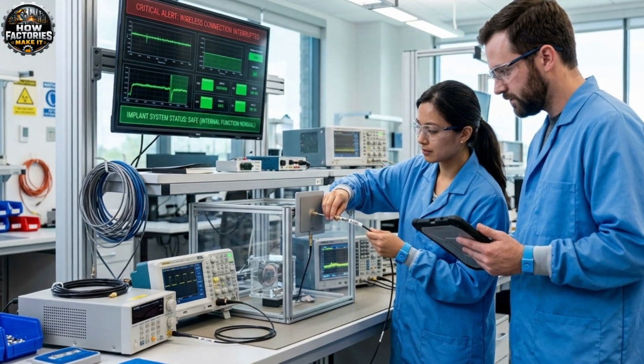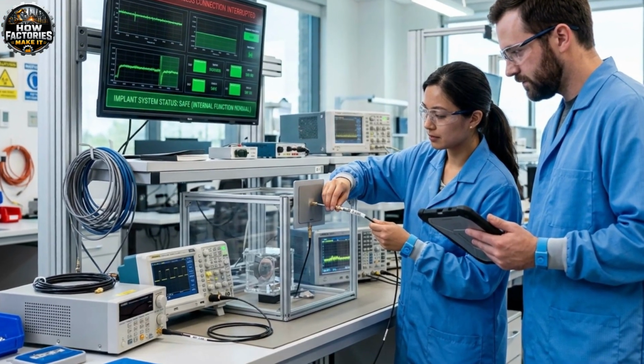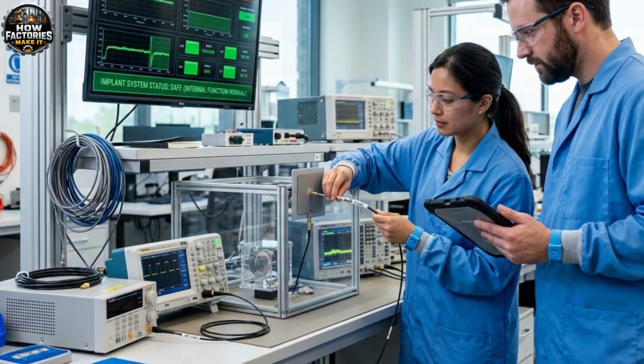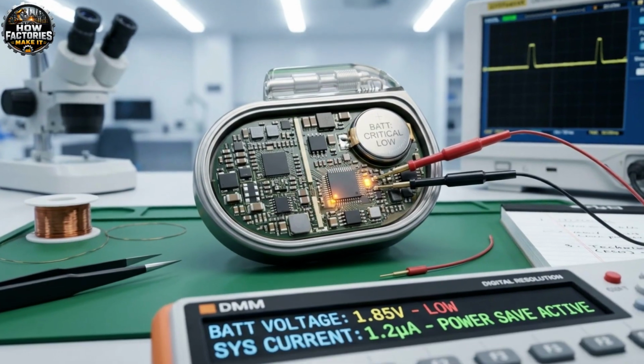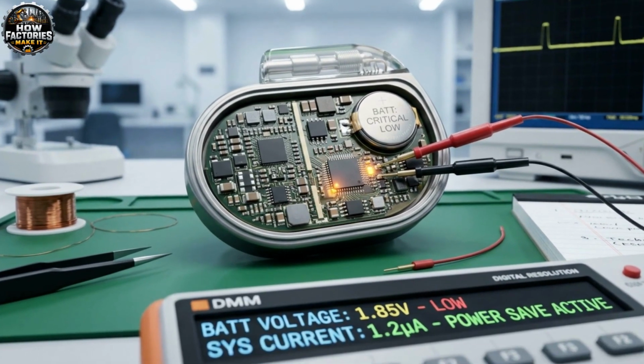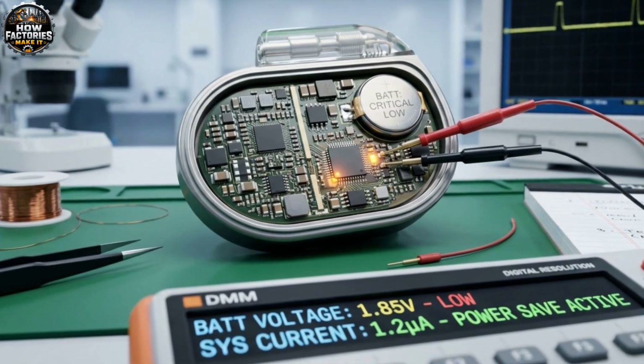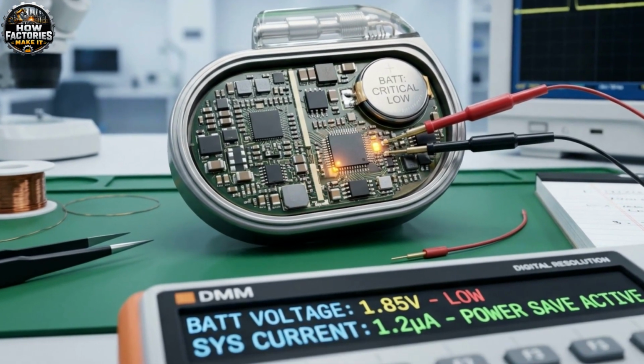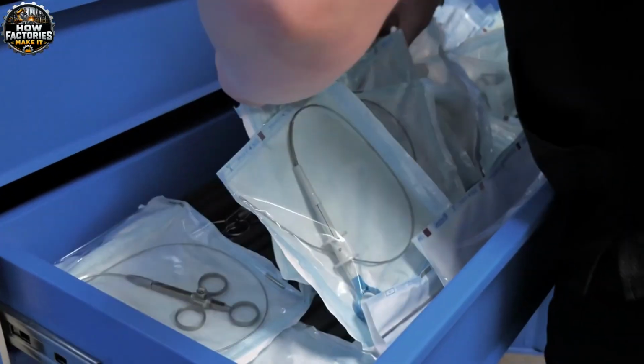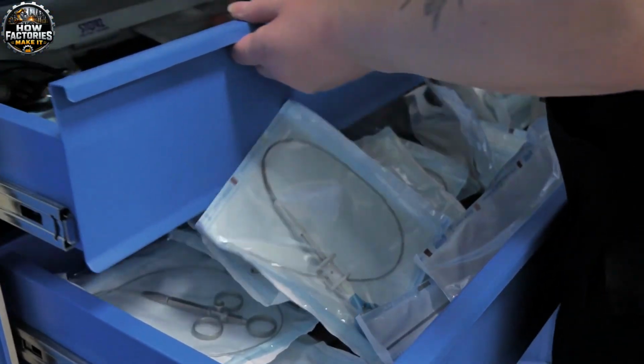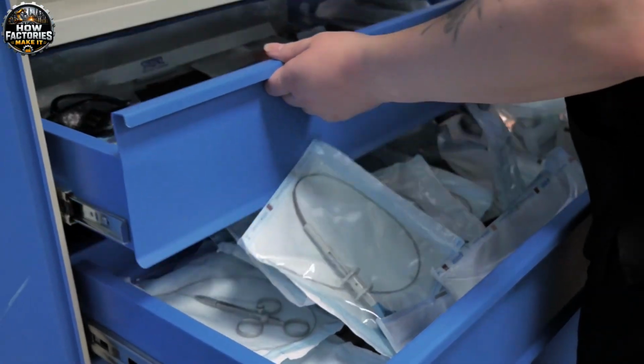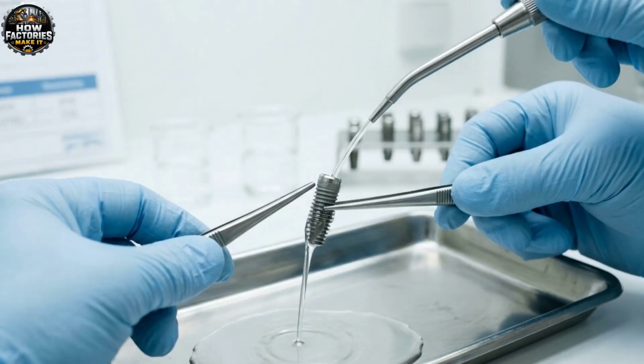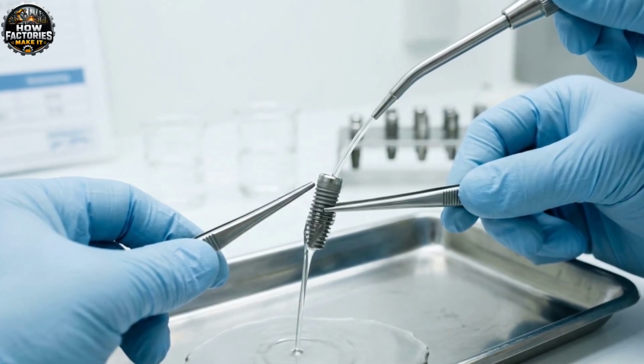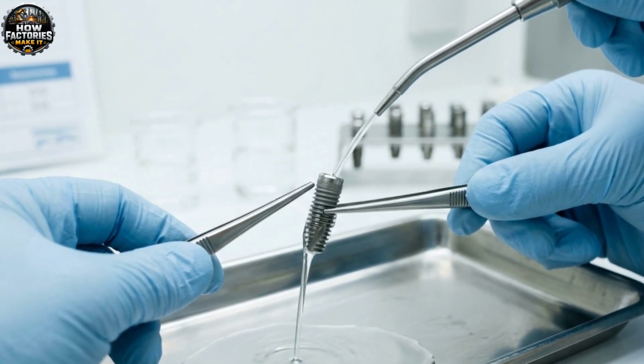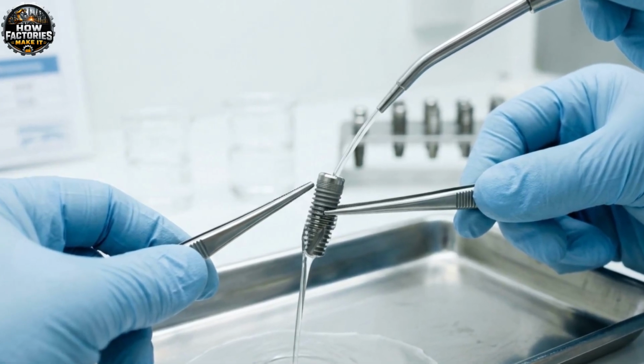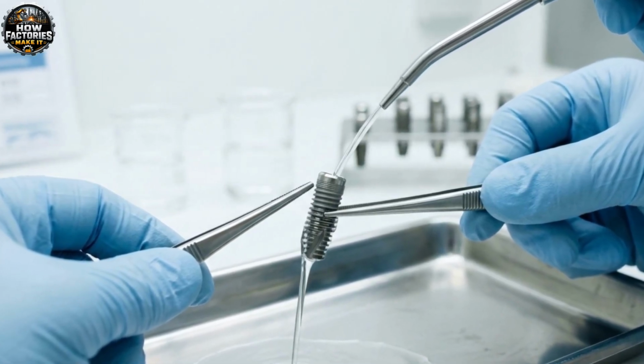Microscopic particles and manufacturing residues must be removed without damaging the delicate threads. The implant is cleaned using tightly controlled processes compatible with its polymers, electronics and coatings. It is then packaged inside a sterile barrier system designed to protect it during transportation and storage. The sterilization method must destroy microorganisms without degrading the battery, electrode coatings or flexible thread materials.